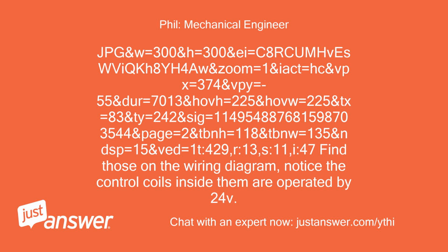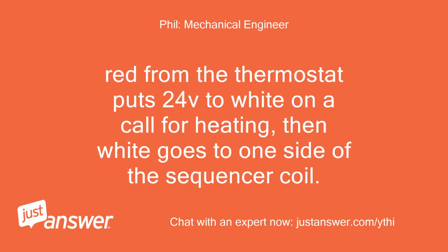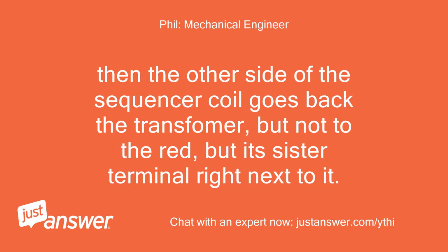Find those on the wiring diagram. Notice the control coils inside them are operated by 24V. Red from the thermostat puts 24V to white on a call for heating, then white goes to one side of the sequencer coil. Then the other side of the sequencer coil goes back to the transformer, but not to the red, but its sister terminal right next to it.